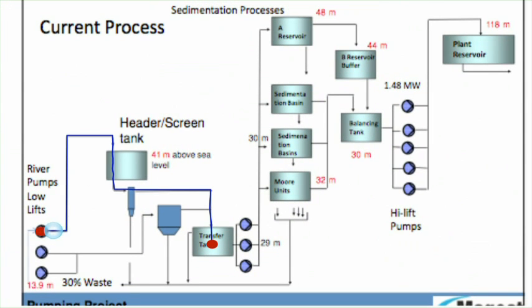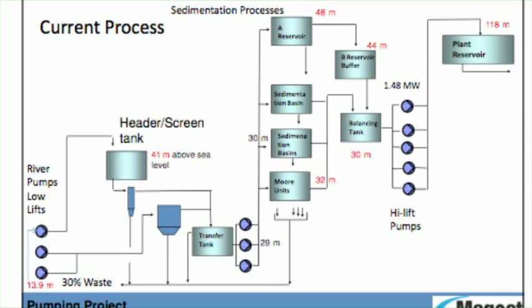This is the original plant configuration. Pump from the river, about 3 parallel pumps up to a header tank that goes down by gravity to some cyclones, which separate out the heavy waste that comes from the river. Obviously there's a lot of stone and grit that has to be removed. The accepts from that go into a transfer tank, and parallel to that there was another grit chamber. Then they process the water through the rest of the plant. They go through sedimentation processes where in principle you're just allowing the dirt to settle out, and the accepts overflow and proceed forward through the process, and then it gets pumped up to the mill.